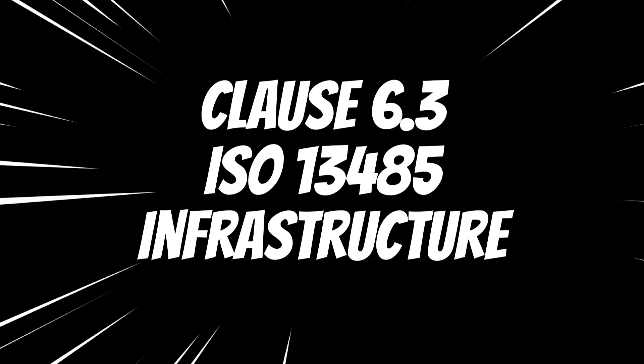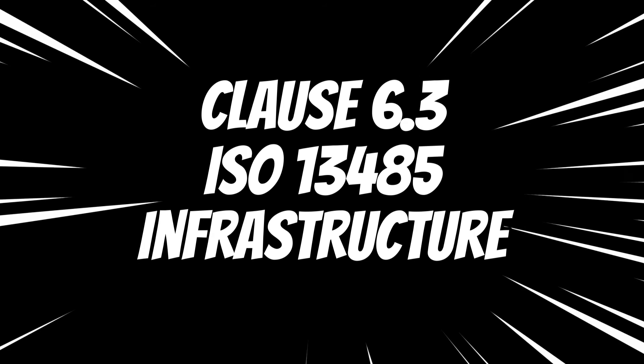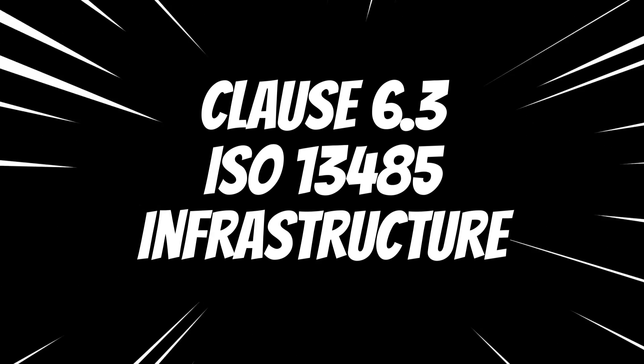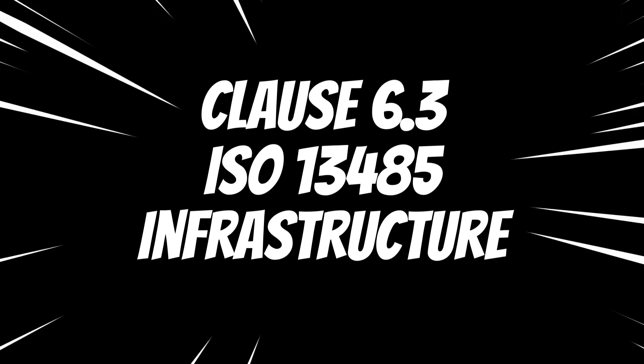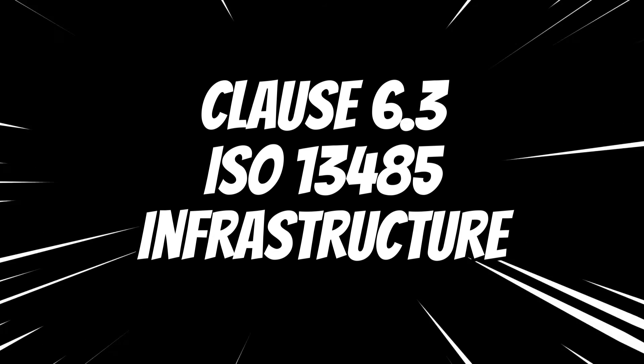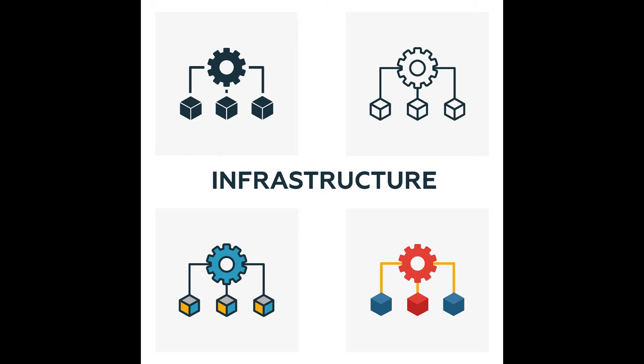Clause 6.3 of the ISO 13485 standard outlines the requirement for infrastructure in a medical device quality management system. Infrastructure includes facilities, equipment, and environment necessary for the operation of the QMS.